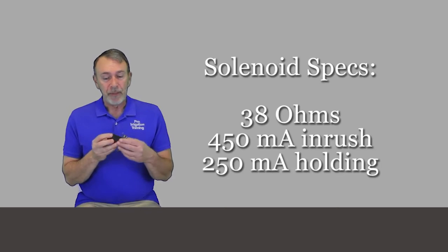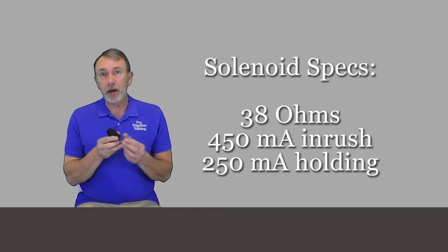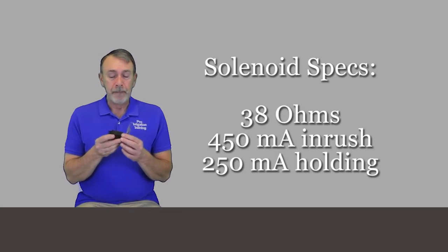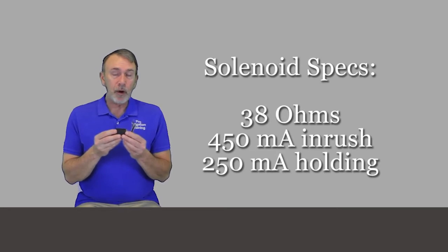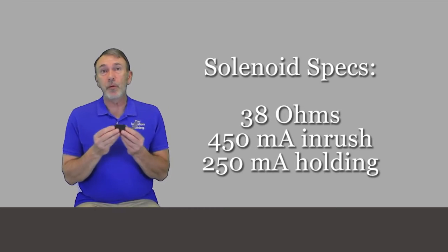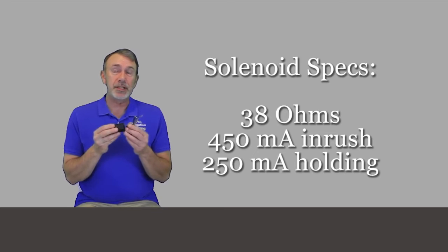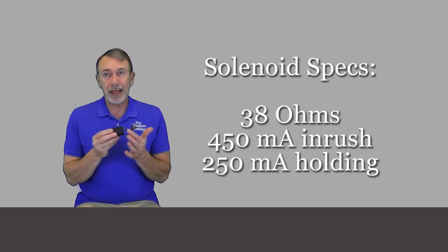In the past when I've measured these in the field, 55 is relatively common to find on this. The inrush amperage on this, which is the amount of electricity it takes to open it up, is 450 milliamps and the holding amperage is 250 milliamps.